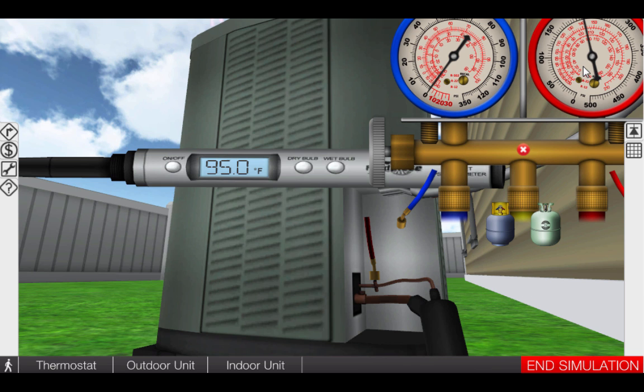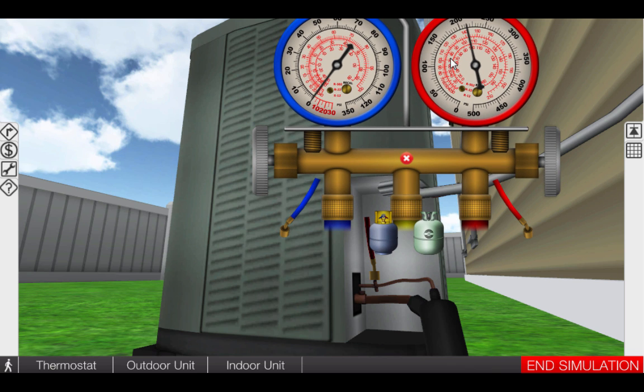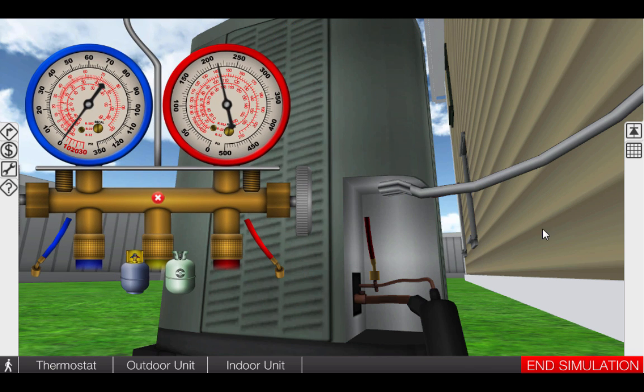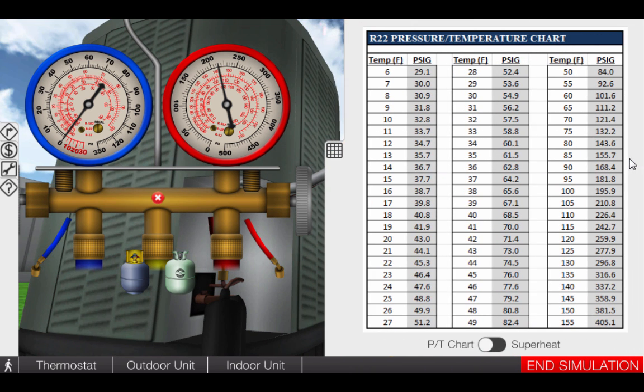Let's take a look at the temperature pressure chart. We'll store the thermometer away and move the gauges to the side. This icon on the right will open the temperature pressure chart. Following 212 PSIG, we can see approximately 210.8, which is fairly close. We can see that the refrigerant is condensing at 105 degrees — only 10 degrees above the outdoor temperature. This is a lower than normal high side pressure on the air conditioner.